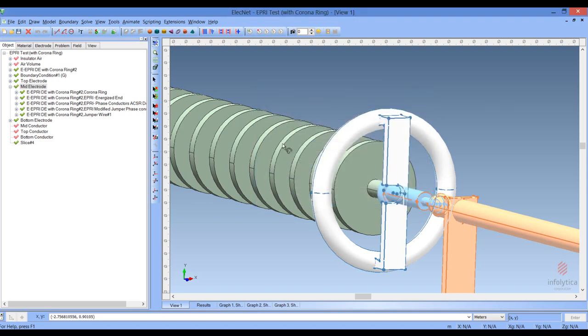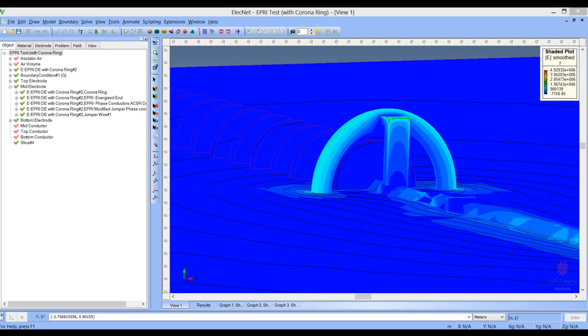Let's view the solution for this model. As we can see, the corona ring seems to be doing its job. The highest stresses are on the corona ring and not so much on the energized fitting, and so this would protect the whole structure from a lightning strike or high voltages.